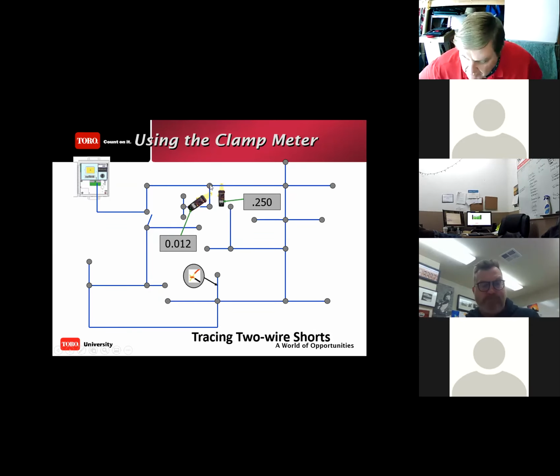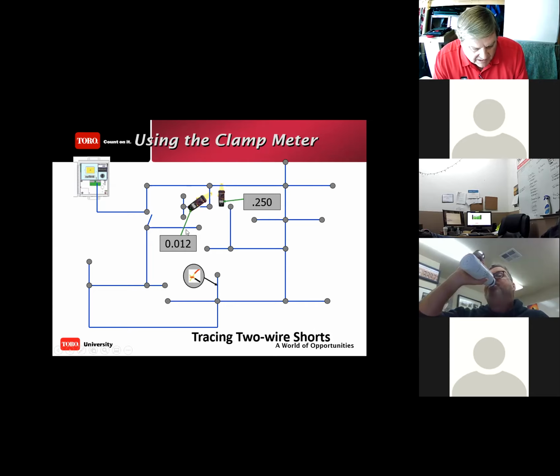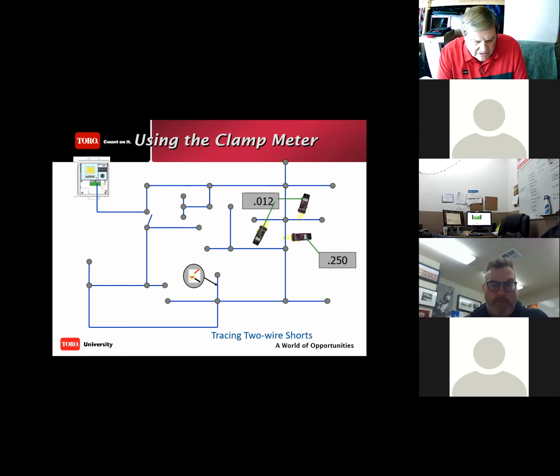You will have a minimum of 6 wires in that valve box, meaning you will have 6 wire connections in that valve box. This is a great place to put the isolating device in there. So now it can have a switch that turns that power on, a switch that turns that power on. So you can isolate to see where the problem truly lies. Now, if you're using your clamp meter, I see 0.012 going down here. That's good. 0.250, that's high. I know my problem is off to my right. And just follow the path through and work your way through the system.